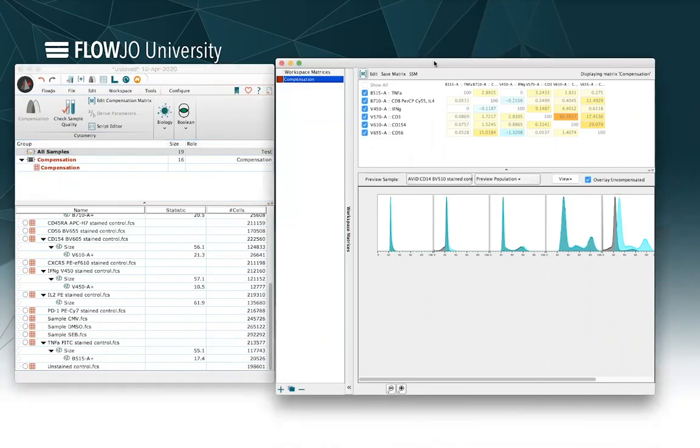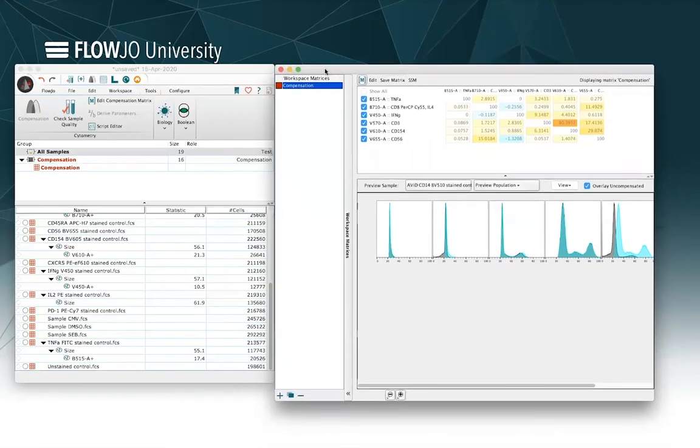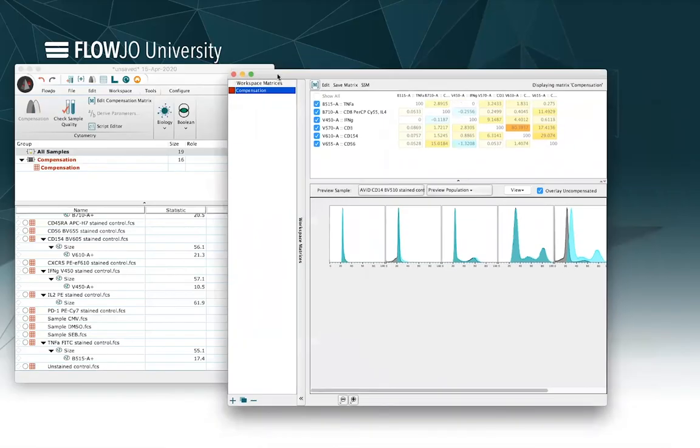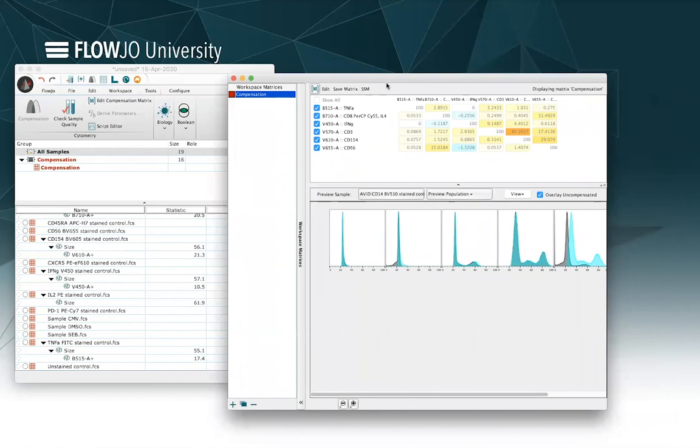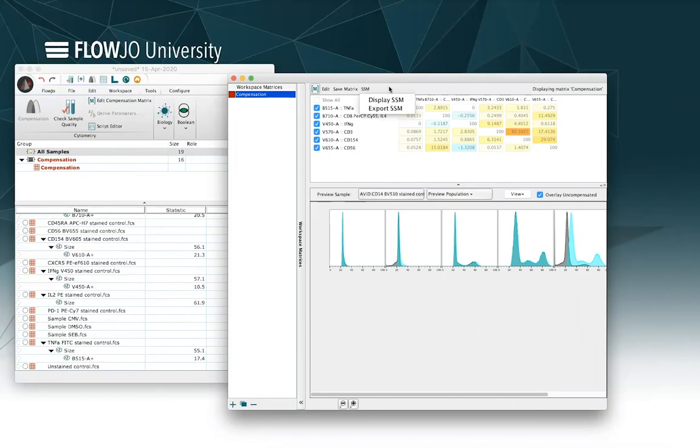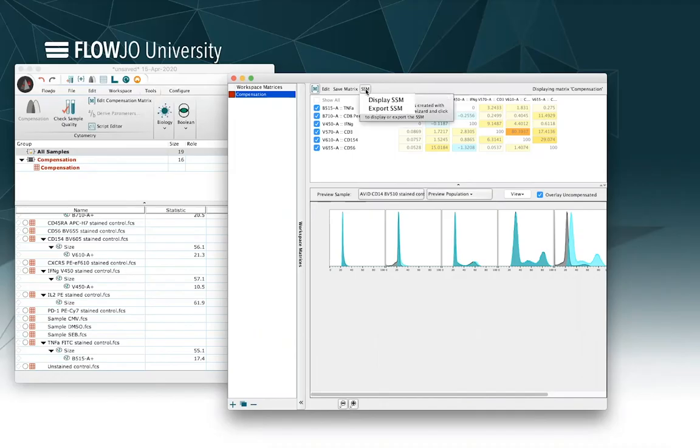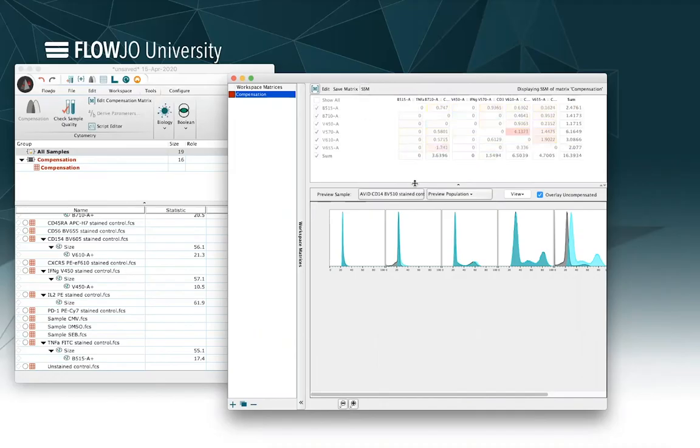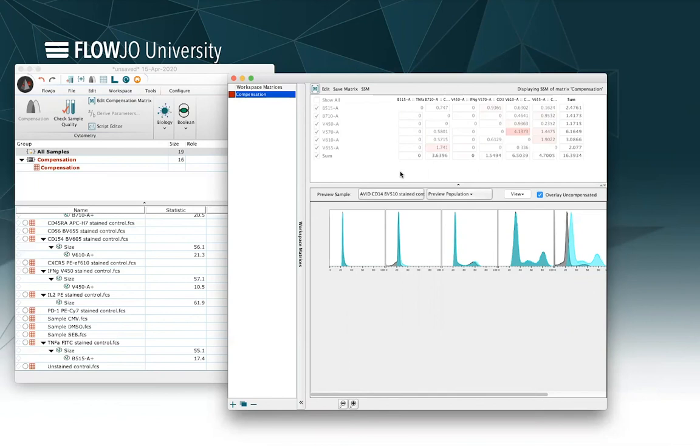Last thing I'd like to point out here, there are a couple other options for compensation matrix correction. If you have any questions on that please reach out to FlowJo at bd.com and we'll be happy to answer any questions you might have going forward. You may also want to double check your SSM. If you're doing things like characterizing your machine over time or you want to compare with somebody else's panel, you can look at the SSM that's generated for your compensation by just clicking that little SSM option and then choosing display, and that will display the SSM that's been calculated, or the spillover spreading matrix, associated with the error in compensation for your data.